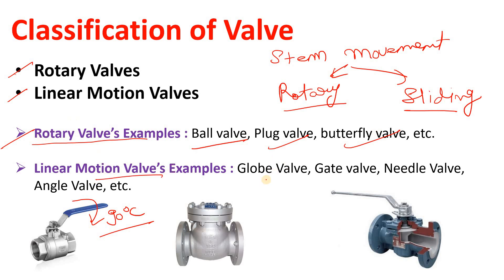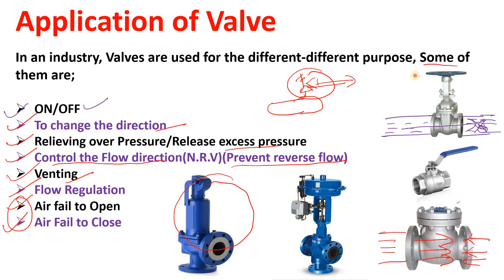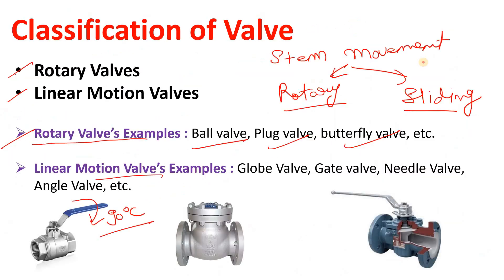In linear motion valves, you open the valve by giving an anticlockwise motion, which moves the stem linearly to open the valve — that is why these are called linear motion valves. Examples include globe valves, gate valves, needle valves, and angle valves. For a plug valve, you simply turn it — whether to open or close — making it a rotary type. For linear motion valves, you must provide anticlockwise or clockwise rotational motion that translates to linear stem movement.